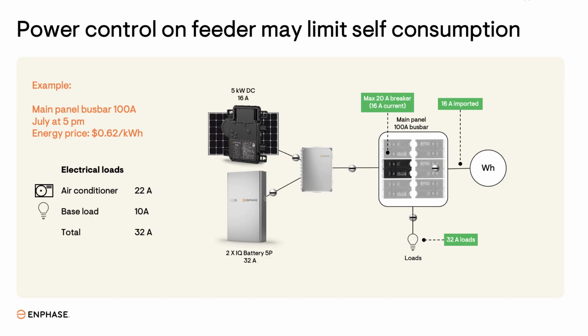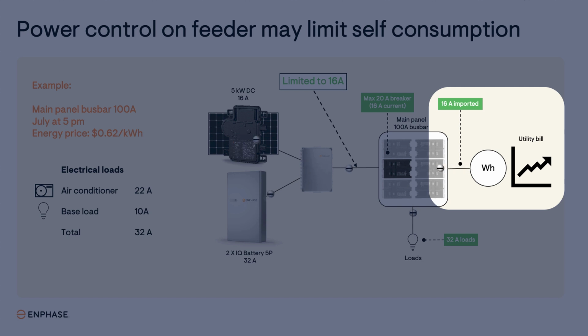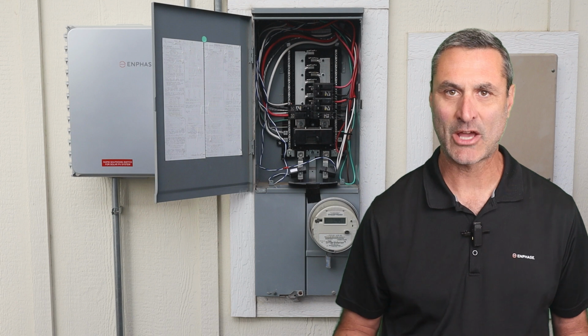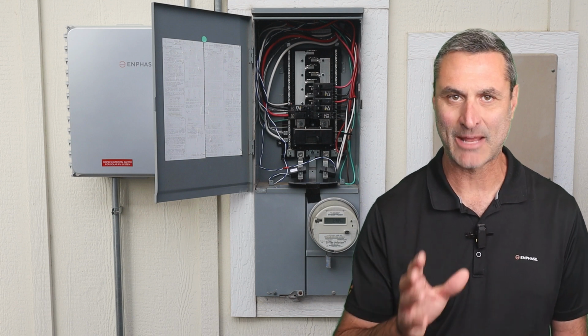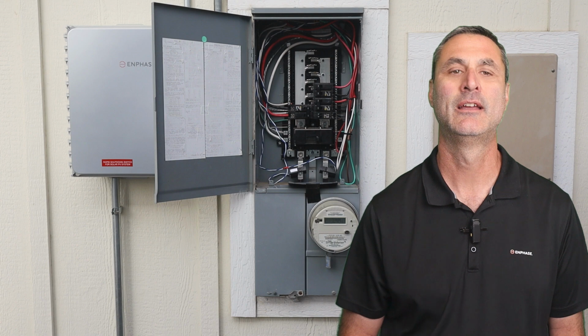Let's look at an example without Busbar Overload Control, where the backfeed breaker is limited to 20 amps by the 120% rule. It's July at 5 p.m., and utility rates are at their highest at 62 cents per kilowatt hour. The home's air conditioner is using 22 amps, and the base load is 10 amps, totaling 32 amps of power draw. If solar and the battery are limited to supplying only 16 amps, then the other 16 amps, or half of the power demand of the home, would be supplied by the grid at very high prices. In this case, without busbar overload protection, the homeowner would be paying for that power deficiency at full peak pricing.